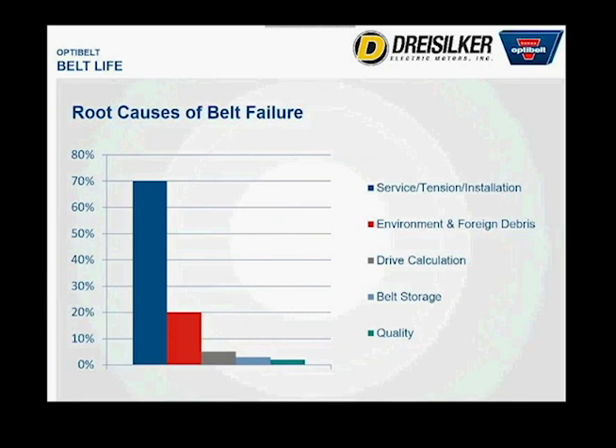So the reason for this, 70% of it from what we've seen, is service tension and installation issues. You install it with too low of tension, you install it improperly, you install it with a screwdriver and damage the belt, or you just didn't have time to tension it properly and align the pulleys. This causes extra heat, extra wear, and the belt fails early.